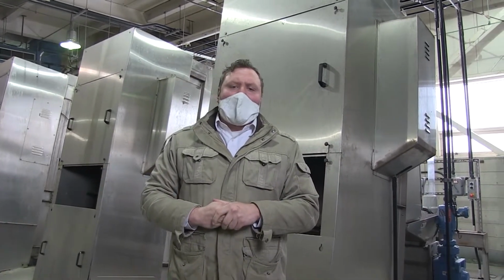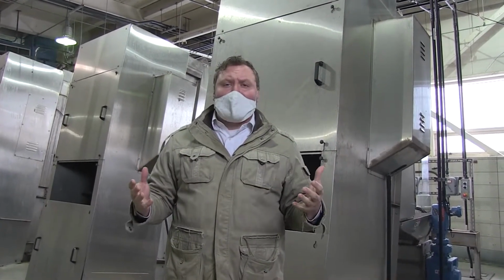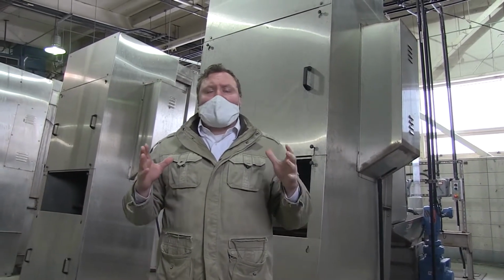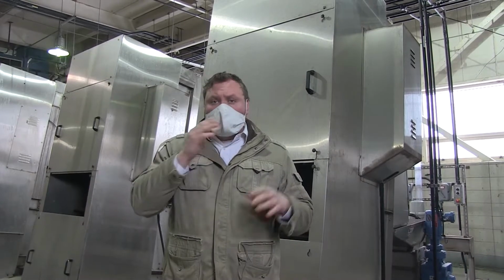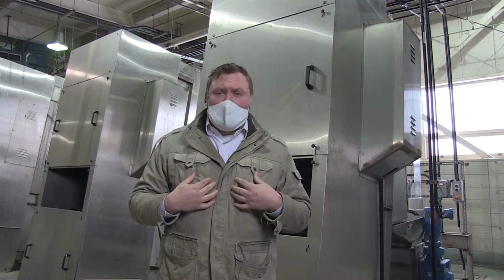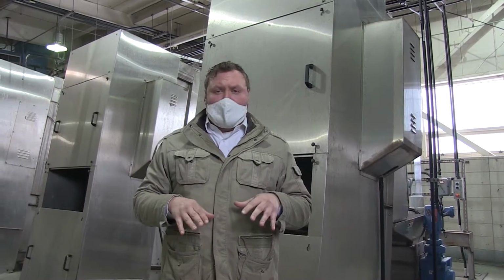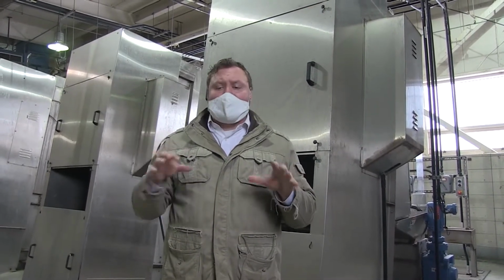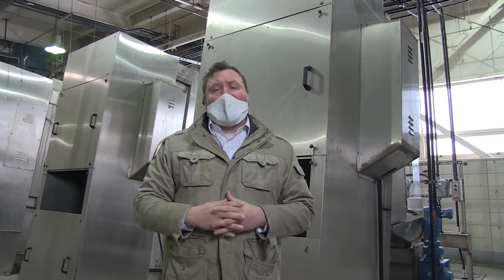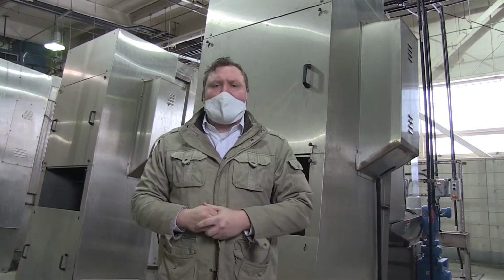So that's the goal. Another industry that discharges to us is Global Foundries. They're a semiconductor plant. They make chips that are in your phones, in your computers. They discharge about 3.5 million gallons a day, so they're a large user. Their main constituent that we have to deal with is actually ammonia, right? We have an ammonia permit limit so that the Hudson doesn't get a large amount of ammonia, which is actually toxic. So we take in their ammonia, we treat it. That treatment process typically happens in our activated sludge basin, so we'll talk about that when we get there.